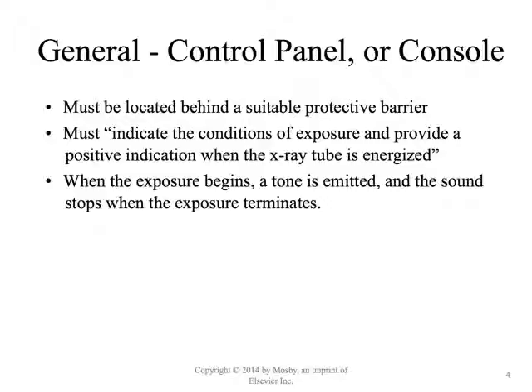for whatever equipment we're operating. And that control console will be behind an appropriate amount of shielding. So if we're dealing with diagnostic X-ray, I think it's like 1.5 feet of concrete, or I think it's 1.5 millimeters of a lead equivalent, so that it shields us from secondary radiation. There'll also be some kind of elbow shape or something, either a door that you go in or something that allows you that while you're standing at that control console, you're not being exposed to anything more than background radiation.